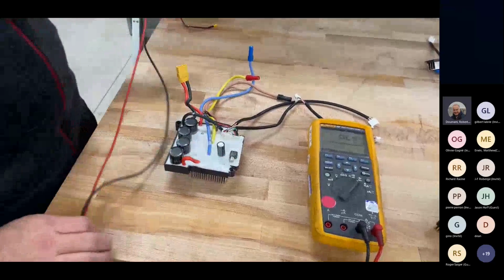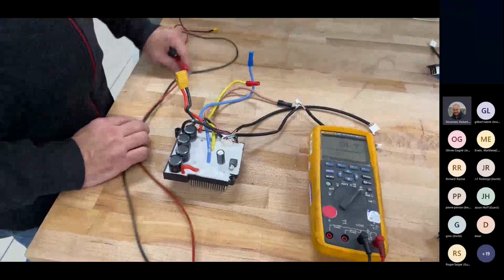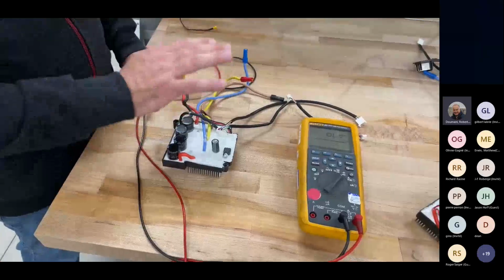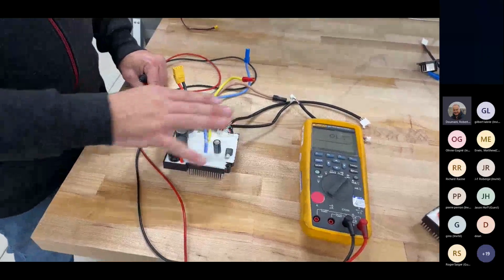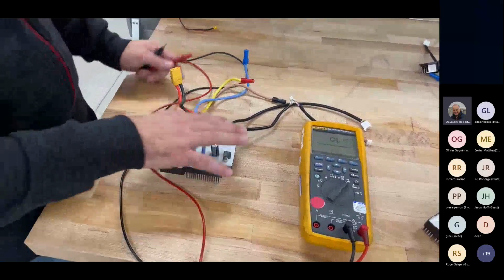That's the only test on your main PCBA. If you're outside of the 0.450 to 0.550 range, then this circuit is bad and needs to be replaced.